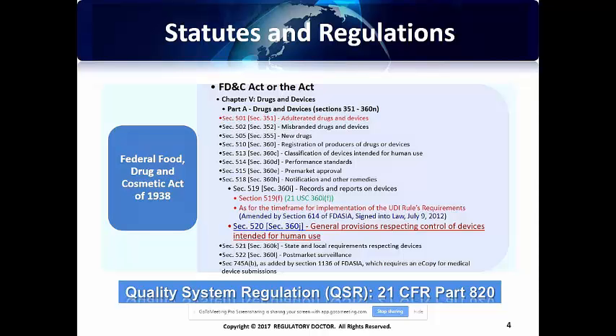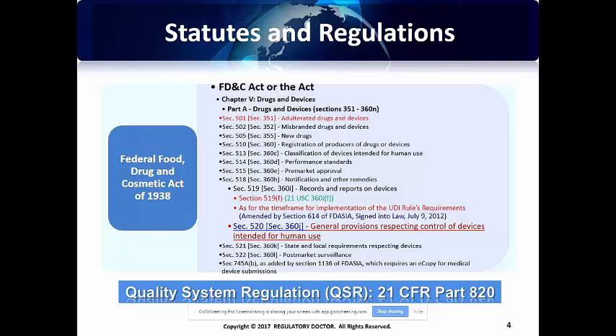Over the years, there have been a lot of amendments made to the FDCA. For example, there is a recent law enacted on July 9, 2012 — the FDA Safety and Innovation Act, known as FDASIA — that amended various sections of the FDCA. For example, FDCA Section 519(f) was amended according to FDASIA regarding unique device identification. Additionally, FDASIA Section 1136 amended FDCA Section 745A regarding e-copy requirements for medical device submissions.